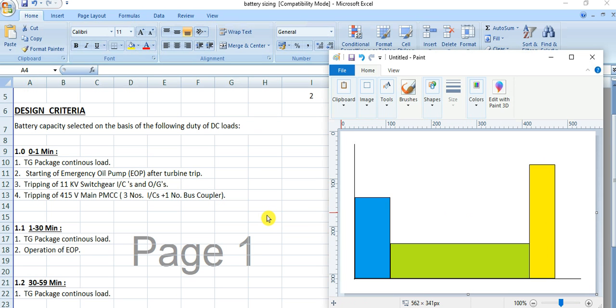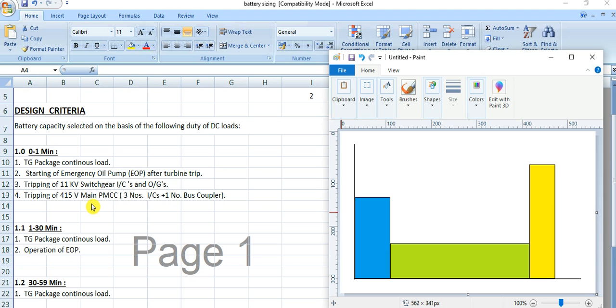For the 0 to 1 minute load, the loads include: the TG package continuous load, starting of the emergency oil pump (EOP), tripping of 11kV switchgear incomer and outgoing feeders, tripping of 415V Main PMCC, and the incoming bus coupler breaker.